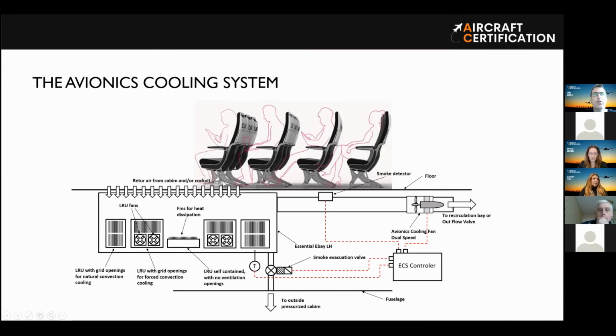of the electronics. So people breathe air at a temperature not higher than 29 degrees C, but the electronics can work well up to 70 degrees C. So the ECS controller needs to monitor if the temperature in the bay is below 70 degrees C. In case we have an obstruction of the inlet of the bay, the ECS controller will monitor its temperature. If the temperature exceeds the acceptable temperature for the electronics, it will put a message for the pilot, indicating that we have a problem in the system, and the pilot needs to take an action, okay? And the flow normally is driven by a fan that provides exhaust for the bay.